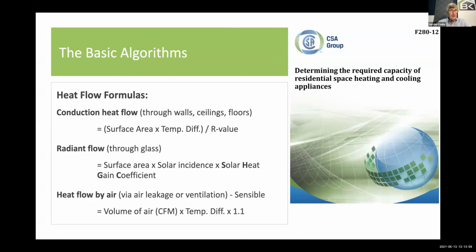It's the surface area. It's not the square footage of the house. It's the surface area of the walls, the surface area of the ceilings, times the temperature difference across that wall, floor, ceiling on the coldest day, or whatever you determine to be the worst day, divided by the R value of that wall. Now, here's first thing we need to understand. We're Canadians. We're trying to be metric. But for whatever reason, we're still stuck on imperial in some key areas. For example, R value. We don't seem to know RSIs very well. So everybody talks about R60 ceilings. So guess what? Since we're going to keep it at R values, everything else has got to be in imperial. So surface areas in square footage, temperature differences in degrees Fahrenheit. You absolutely can adjust these formulas.